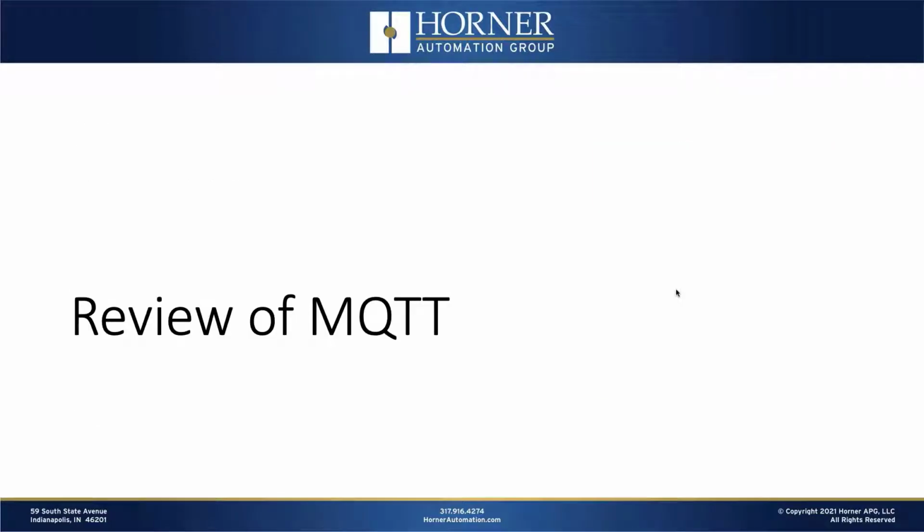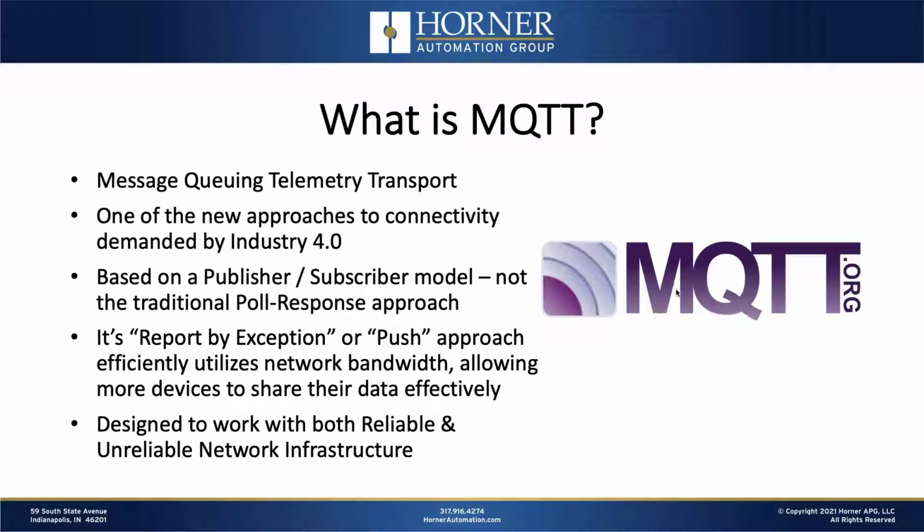Okay, let's start with our review of MQTT. What is MQTT? It stands for Message Queuing Telemetry Transport. Effectively, it is probably the most popular of the new IoT protocols for industrial applications. And it's probably popular for a variety of reasons, including the fact that it utilizes the publisher-subscriber model, which means that it's much more bandwidth efficient than the traditional poll-response approach of something, say, like Modbus TCP.